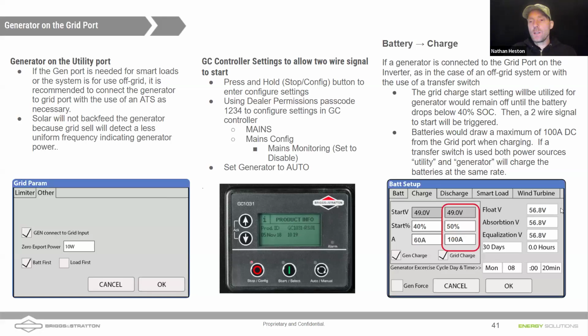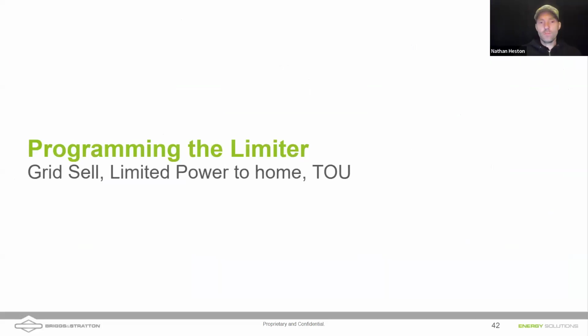And so in this case, if there's a grid down situation and the batteries get below 50%, it will send a 2-wire signal to start. The generator will start up and it will pull power into the inverter through the grid port once that transfer switch kicks over. And it will charge the batteries to a full cycle to 95% or so. Yep. We don't have time in this talk, but there is the ability to use the time of use settings to adjust that, using the generator to charge the batteries to different states of charge.